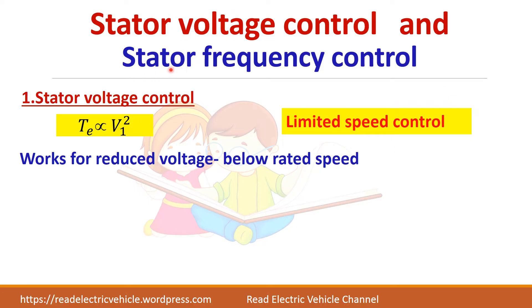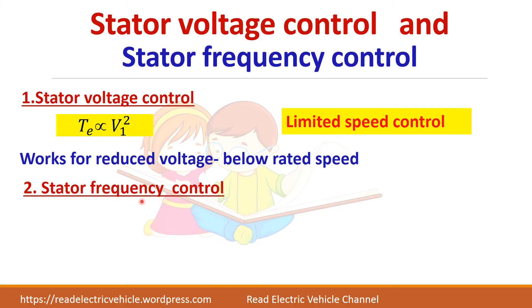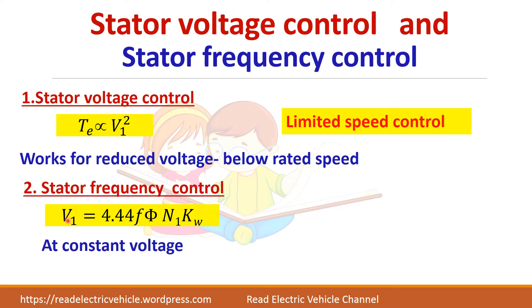The second control technique is stator frequency control. Here the voltage will be kept constant and the frequency of the stator supply will be changed to control the speed. The voltage equation is 4.44 × F × φ × N1 × Kw. Here F and φ are variables. If voltage is kept constant and I change the frequency, flux will also change so that voltage remains constant.